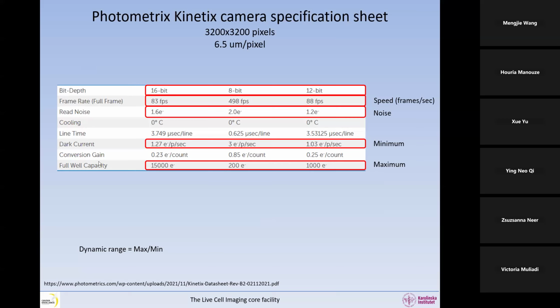As I said, you will see this afternoon with Marie, when we have the workshop with cameras where we compare two different cameras. You will see that the camera pixels are a little bit like a bucket, and you have water falling on them, like the photons are falling on them, and the bucket is filling up. So we want to have a big bucket. If we have a big bucket, we can accumulate a lot of electrons inside before we read it and empty it before the next image.